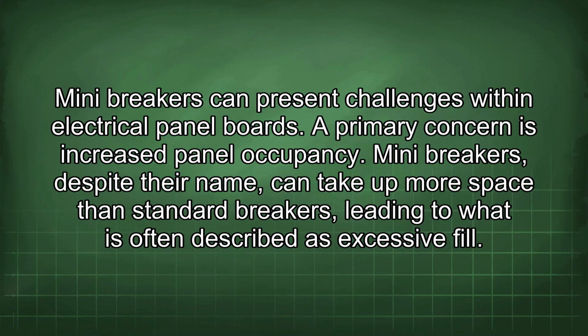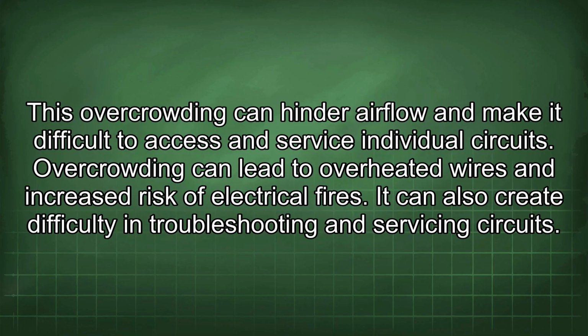Mini breakers can present challenges within electrical panel boards. A primary concern is increased panel occupancy. Mini breakers, despite their name, can take up more space than standard breakers, leading to what is often described as excessive fill. This overcrowding can hinder airflow and make it difficult to access and service individual circuits. Overcrowding can lead to overheated wires and increased risk of electrical fires. It can also create difficulty in troubleshooting and servicing circuits.